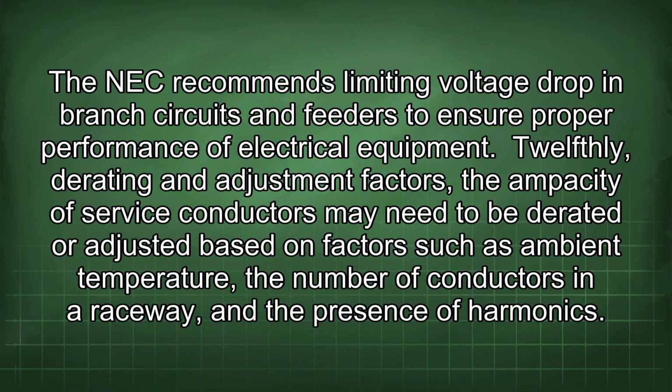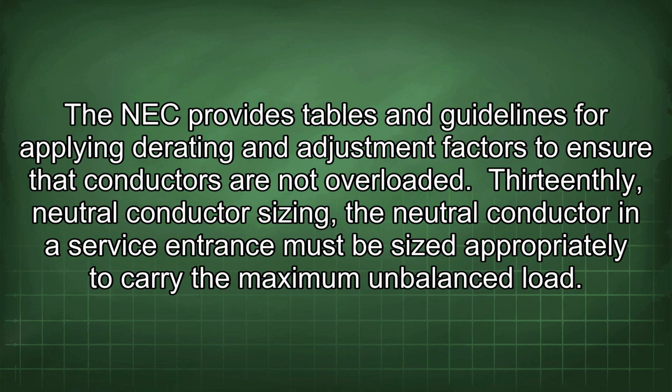12thly, derating and adjustment factors. The ampacity of service conductors may need to be derated or adjusted based on factors such as ambient temperature, the number of conductors in a raceway, and the presence of harmonics. The NEC provides tables and guidelines for applying derating and adjustment factors to ensure that conductors are not overloaded.